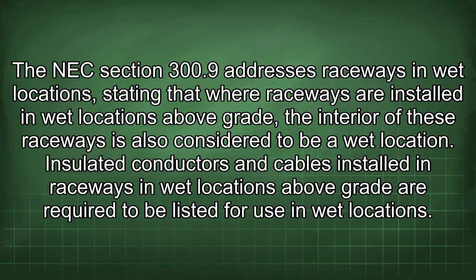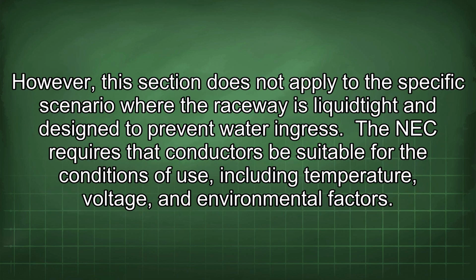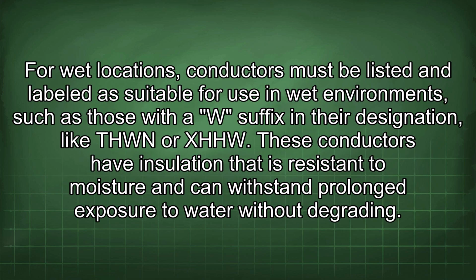The NEC Section 300.9 addresses raceways in wet locations, stating that where raceways are installed in wet locations above grade, the interior of these raceways is also considered to be a wet location. Insulated conductors and cables installed in raceways in wet locations above grade are required to be listed for use in wet locations. However, this section does not apply to the specific scenario where the raceway is liquidtight and designed to prevent water ingress. The NEC requires that conductors be suitable for the conditions of use, including temperature, voltage, and environmental factors. For wet locations, conductors must be listed and labeled as suitable for use in wet environments, such as those with the W suffix in their designation, like THWN or XHHW.